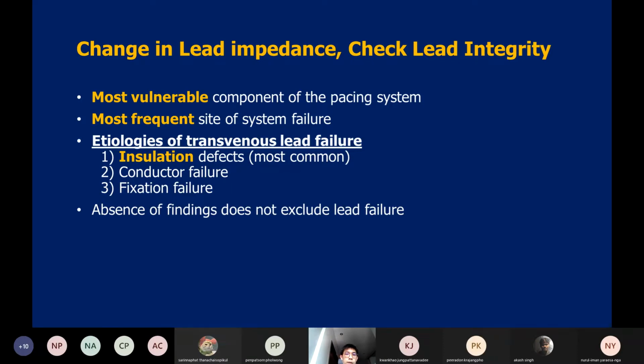A change in impedance indicates that the system is failing. The most common etiology of transvenous lead failure, if the impedance has changed, is an insulator defect. The outside material that wraps around the wire has some defect, like a tear or some leakage, so the impedance would change. Other things that can cause the impedance to change are conductor failure or fixation failure.